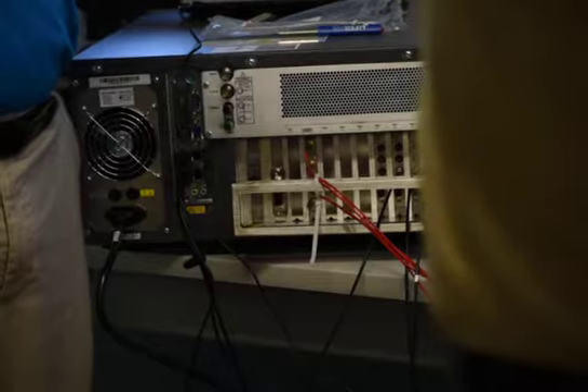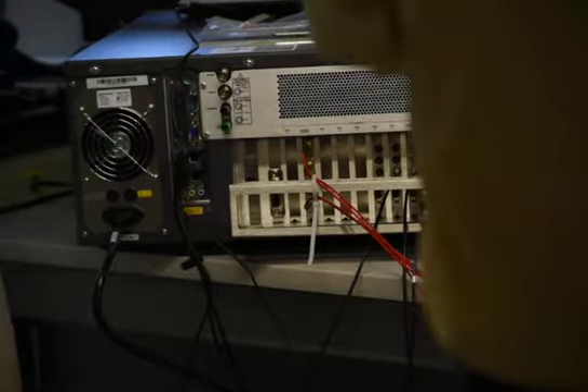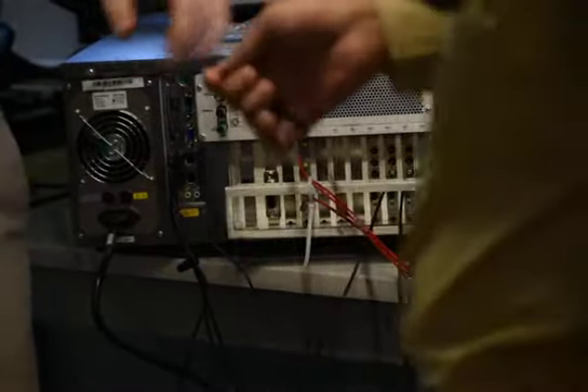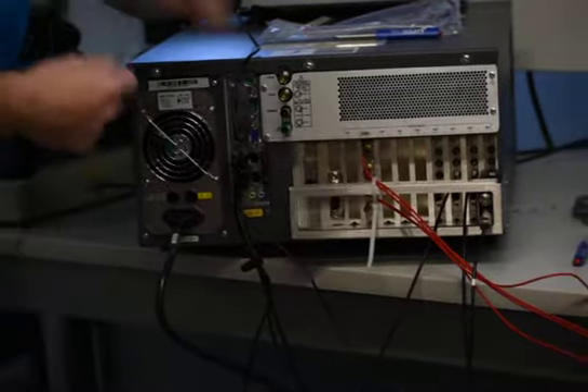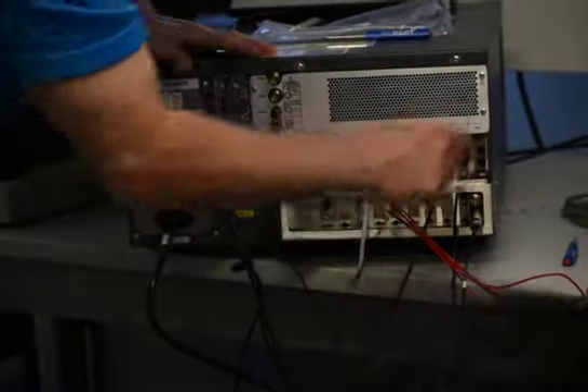Okay, we need this. And those are triaxial cables. This one. Yeah, does everybody understand triax? Yeah? I guess. Don't be shy if you don't, because a lot of people have never seen triax. And do you know why you need triax? You need triax for any current measurements that are less than 100 nanoamps. You're not going to be able to get a low current measurement through coaxial cables, because the triax has a second guard or a second shield on it.